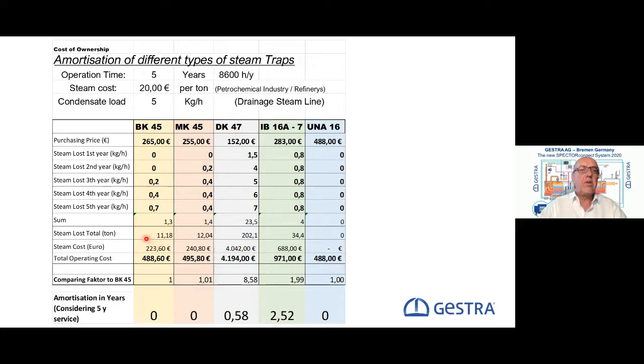At the end, we have a certain amount of loss calculated in tons. The tons multiplied by the steam price we mentioned here mean additional cost for the operation, and now the total operating cost of the steam trap in the first 5 years of operation. We see that the thermostatic steam trap and also the ball float steam trap have a certain level of price, while the thermodynamic steam trap becomes really expensive and the inverted bucket steam trap medium expensive. That means if this is factor number 1, the thermodynamic steam trap is 8.5 times more expensive in 5 years than the bimetallic steam trap.